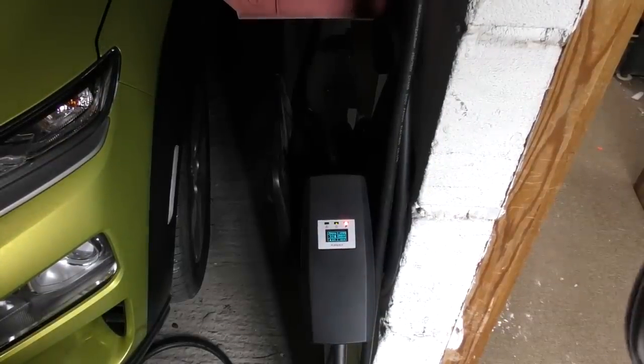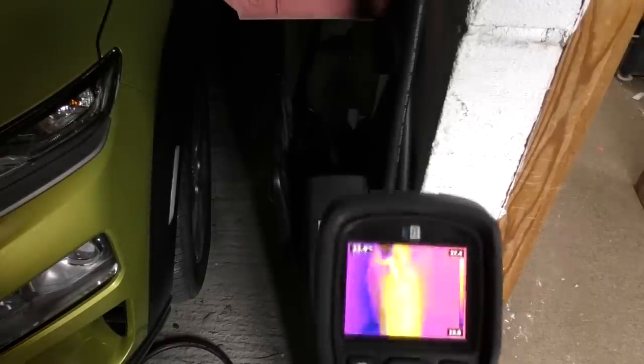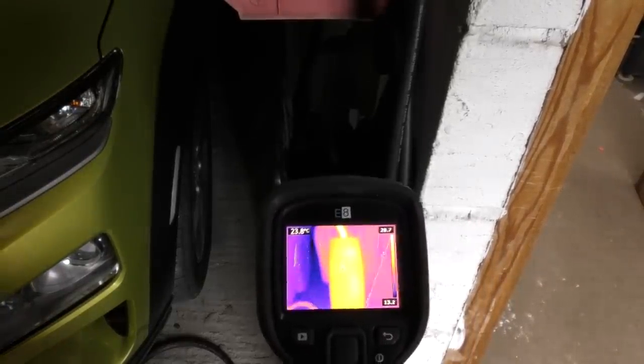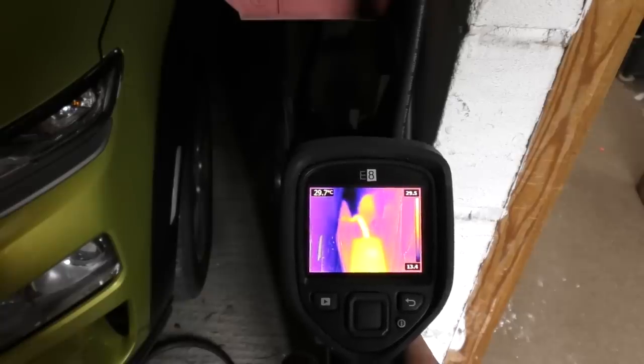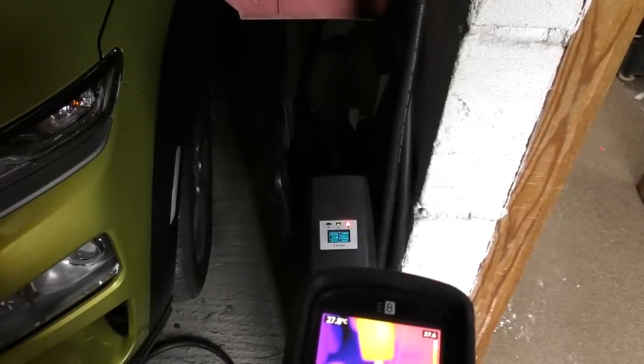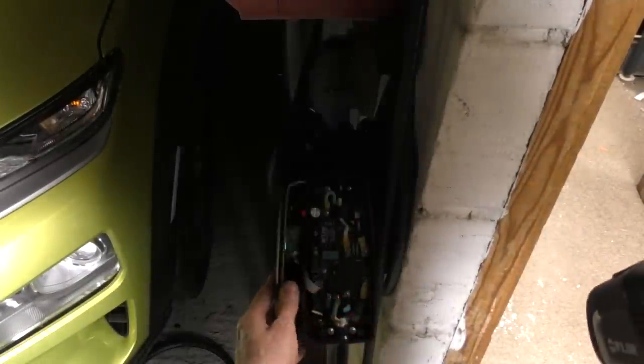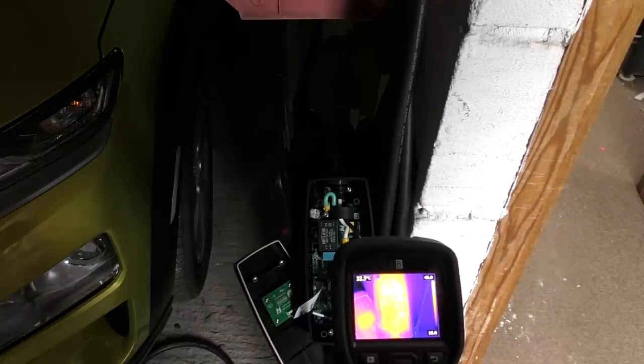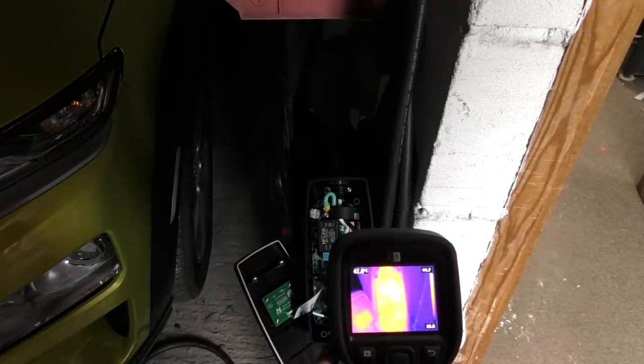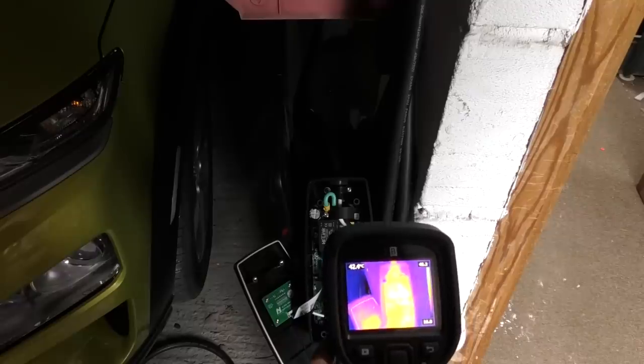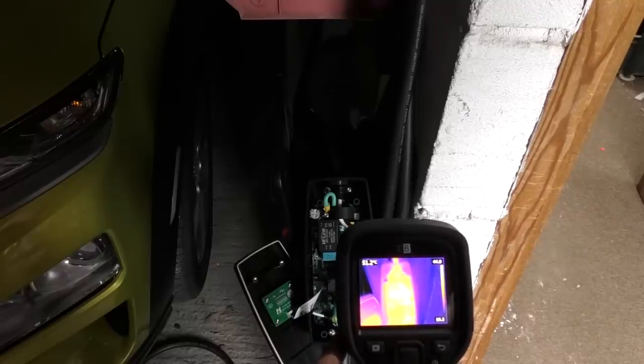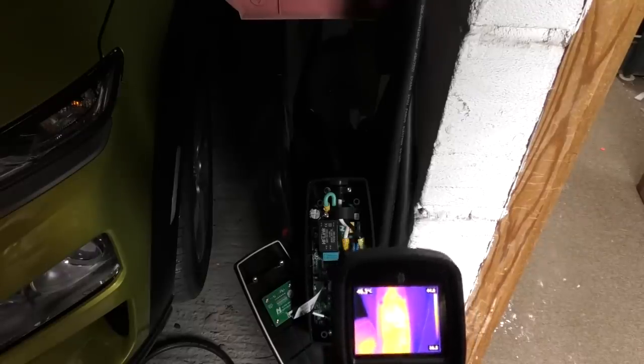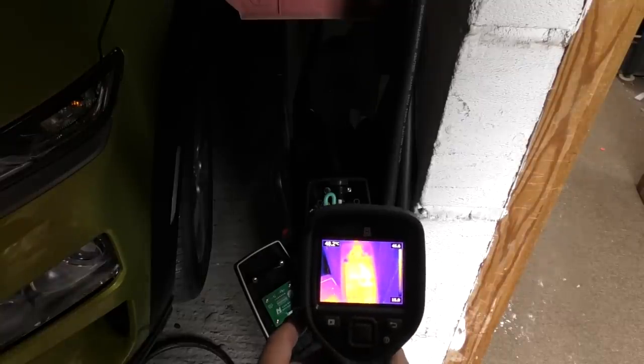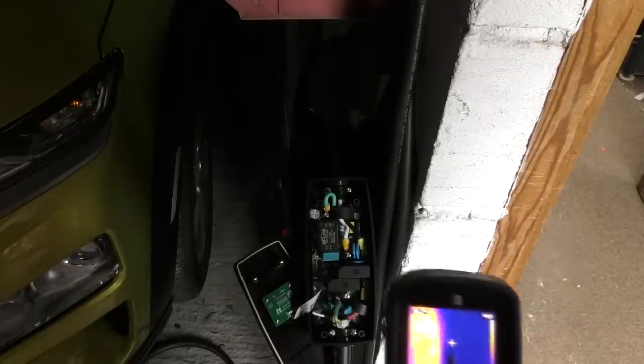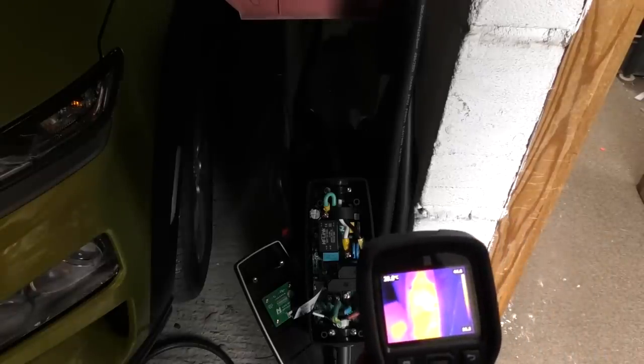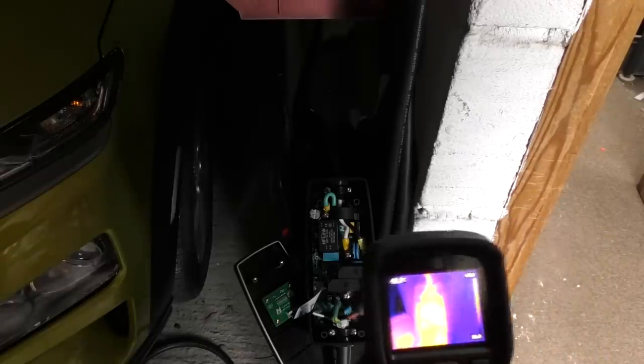This has been charging at 32 amps for about half an hour. The onboard display is saying 33 degrees C, case is 25, input lead 29, output 27, and internally the relays and the connections 35 degrees, which is fine. Power supply modules about 42. The hottest part is actually the resistor that's in series with the voltage measurement transformer, 49 or 50, so that's about the hottest thing. The ambient's about 17 or 18, so I don't think there's anything getting worryingly hot there.